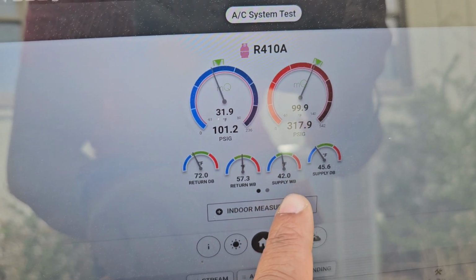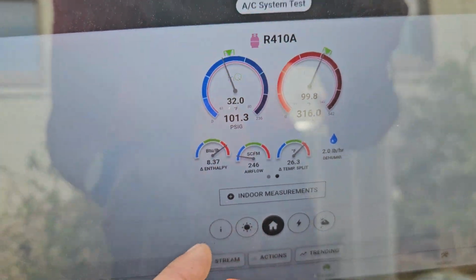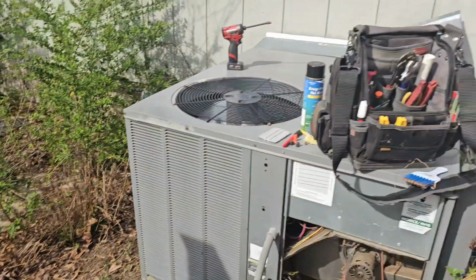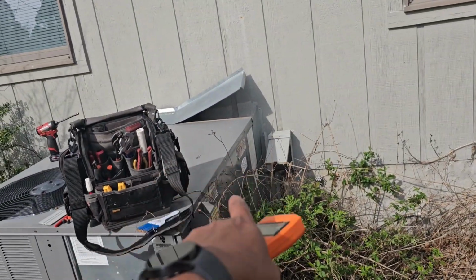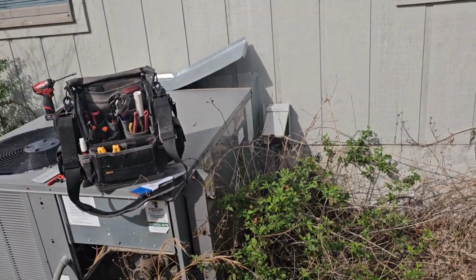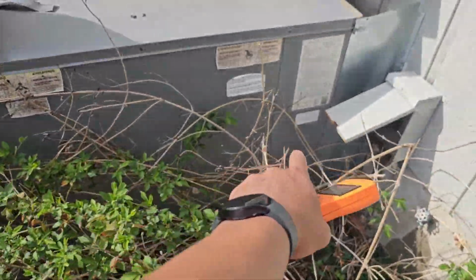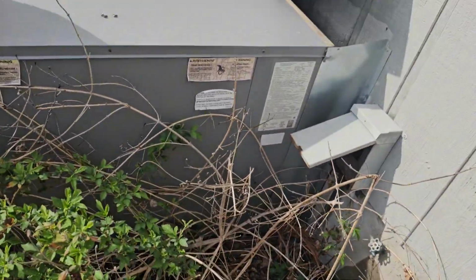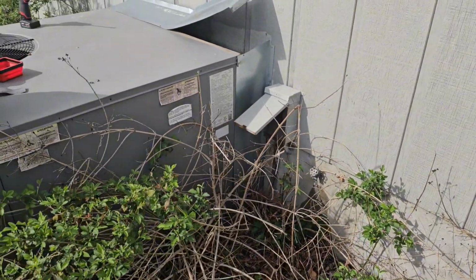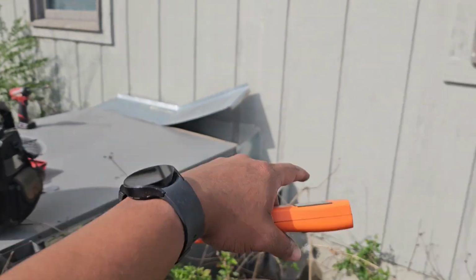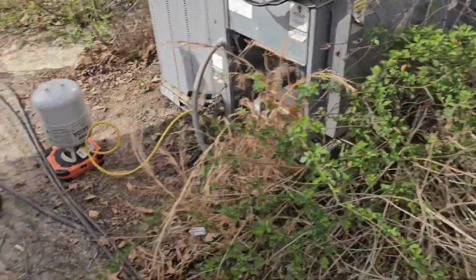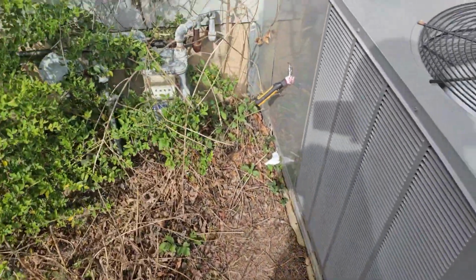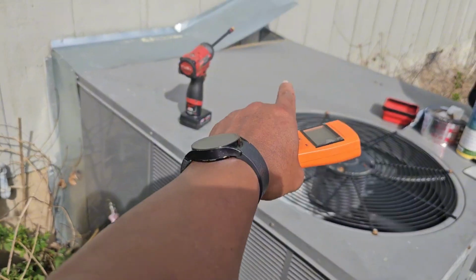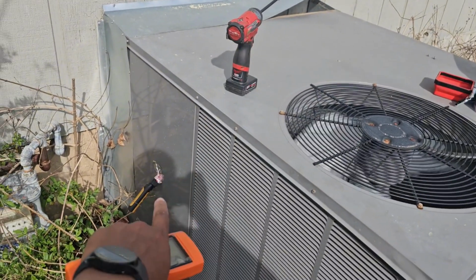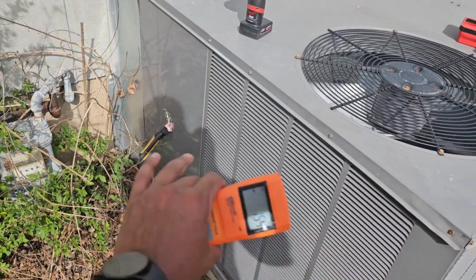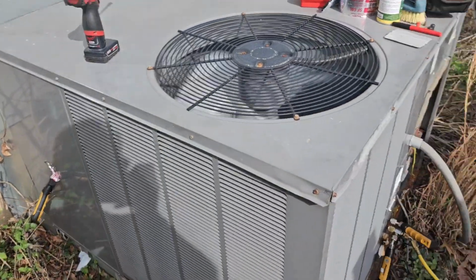We're still looking at about a 26 degree temp split. Even though this is pretty high, I can almost base that off of me being within 4 or 5 feet of the blower motor, probably less. Blower motor right here, probe right here, majority of that force is hitting that way and shooting out, so it's not like cold air is just going across it. If I put the probe at a vent instead, either over here or over there, whichever is closest, it'd probably read closer to 20. There could also be residual cold air emitting from the evaporator coil affecting that. This is just speculation -- I'm just throwing out possible things that could be affecting my Delta T.